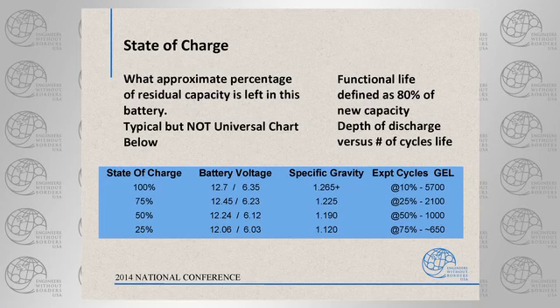So state of charge, how full is the gas tank, if you will. That can be estimated by battery voltage on this chart. It can be better estimated by the specific gravity. If it's a flooded cell that you can actually get in with a hydrometer and measure the specific gravity of the electrolyte. Now, this is a fun one.